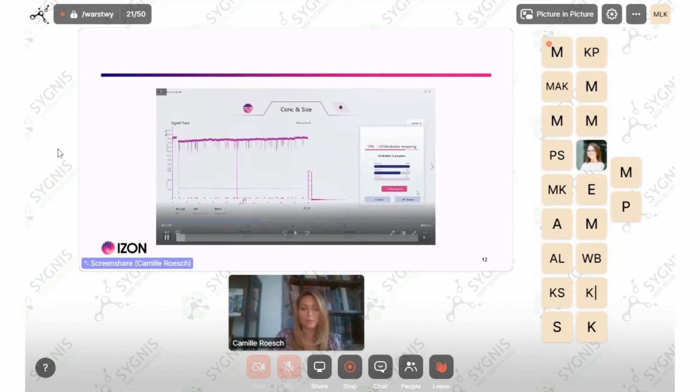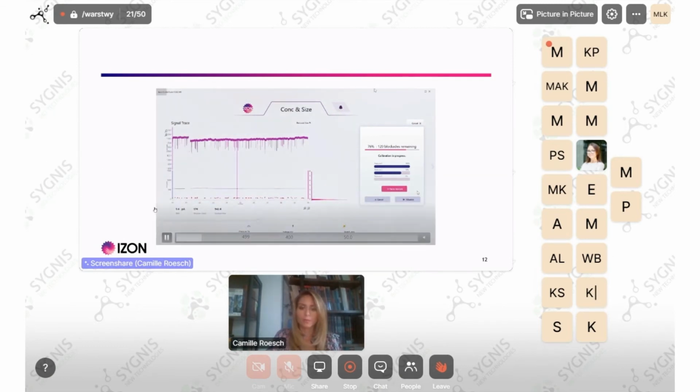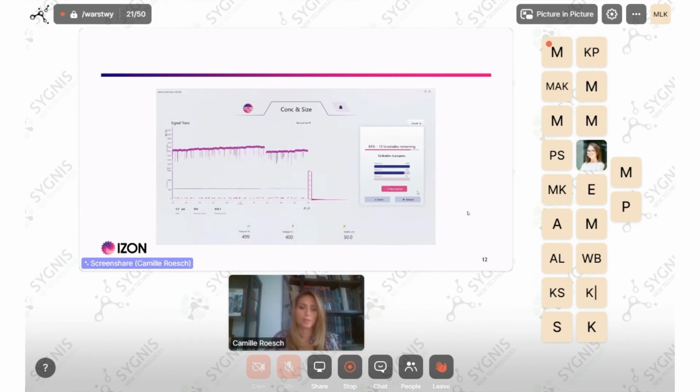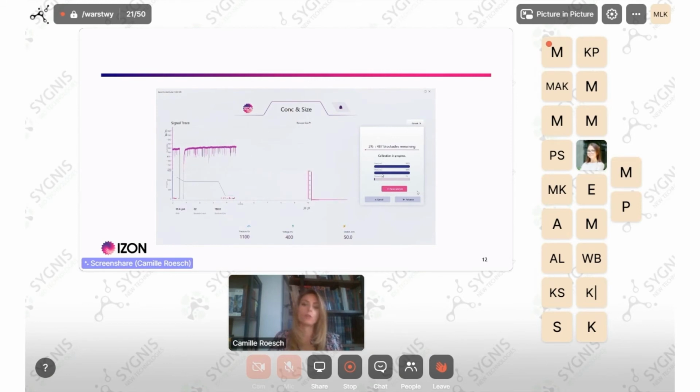This is another video that says pretty much the same thing. So see, we already did pressure 1. We have just done pressure 2, and we're going to be doing pressure 3. Now you can see that the Exoid auto-adjusts to another pressure. You don't have to do anything, but that multi-pressure calibration step is very important when you want to do a good concentration measurement.